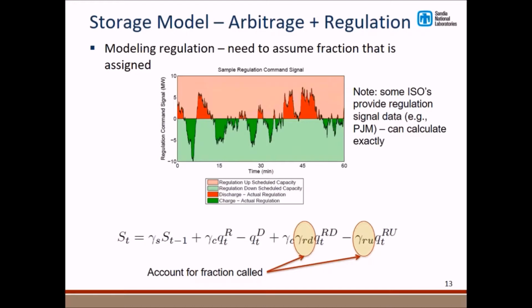The dark green is the actual charging, and the light green is what you were signed up to provide, the 10 megawatt hours. Typically, gamma RU and gamma RD can just use 20% as a guesstimate, and that's usually close enough. We've done sensitivity analysis showing that being off doesn't affect the answer much.